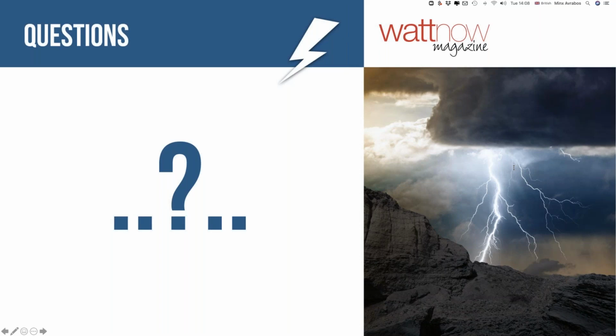Okay, this question is interesting, because in the first place, for a lightning protection system, earth resistance is a meaningless term—we have to talk about earth impedance. But unfortunately, earth impedance measuring devices are quite expensive and complex. Therefore, the standard committees are compelled to have a resistance, a low-frequency resistance limitation value, in the standards for lightning protection systems.